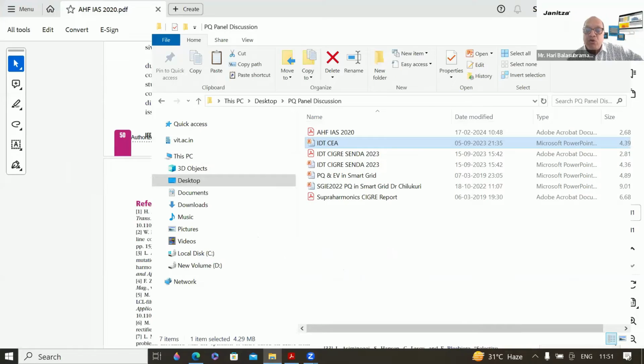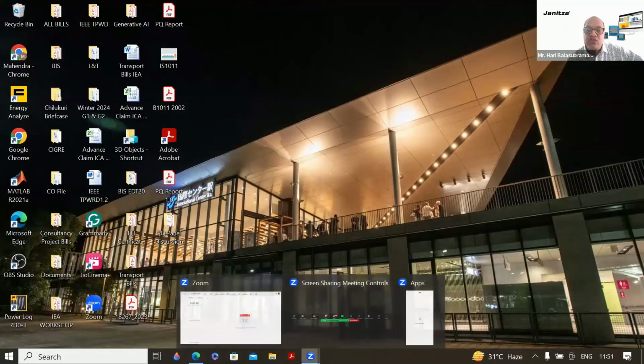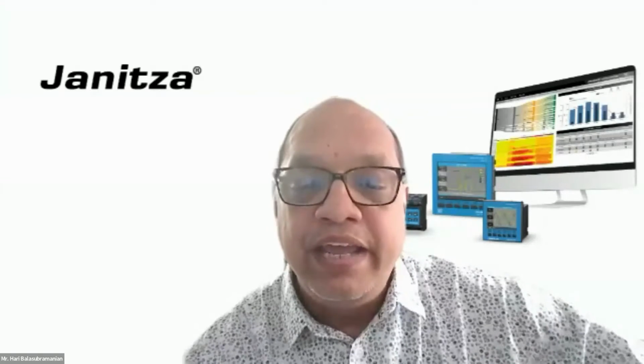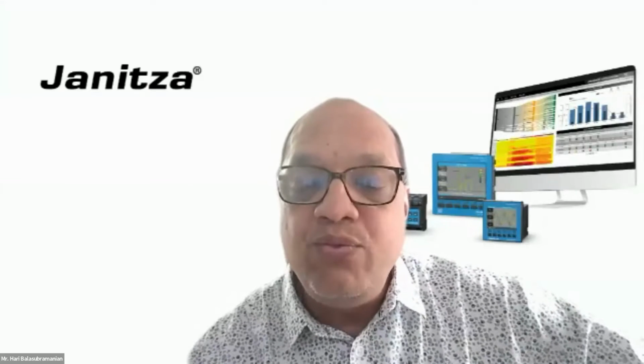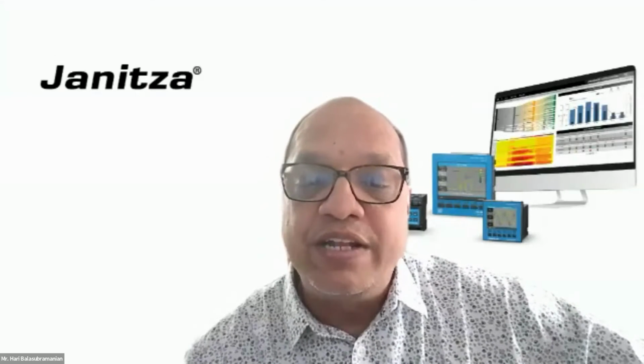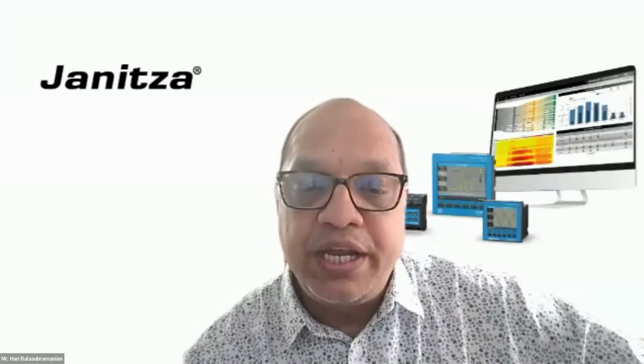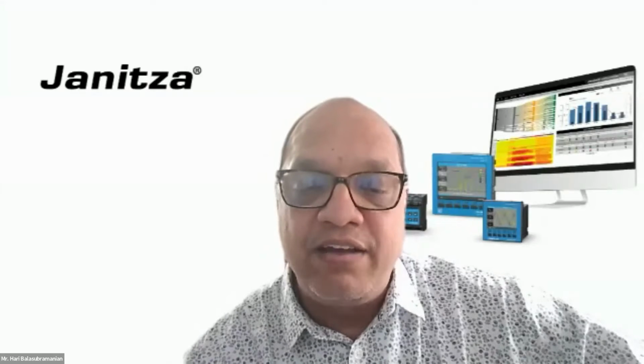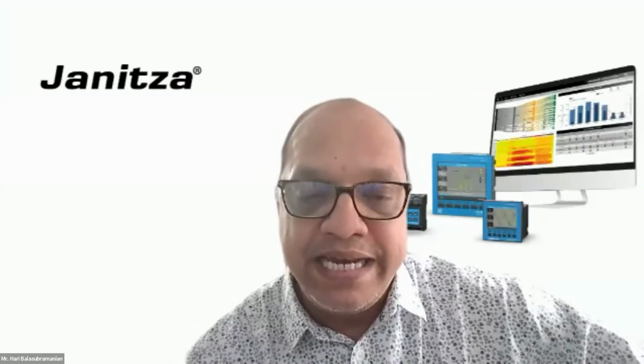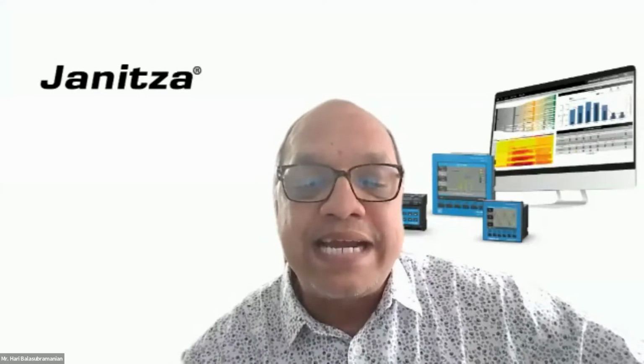Yes. IEEE 519 suggests 3 kinds of tests, on a weekly basis and a daily basis. On a daily basis, we need to take data every 3 seconds. That is for all the harmonics and THD and TDD values, we need to consider every 3 seconds. And for the weekly value, we need to consider data every 10 minutes for the same parameters. Which means the measuring equipment should be able to handle 3 seconds as well as 10 minutes data, and from there you do the statistical evaluation.